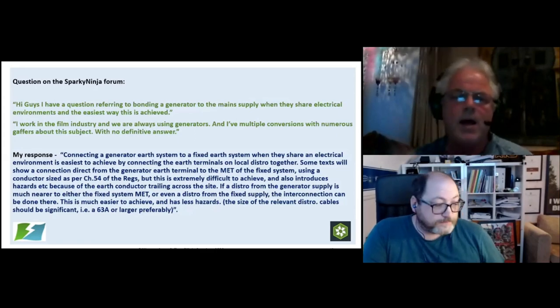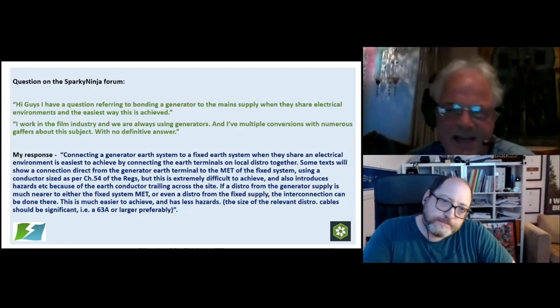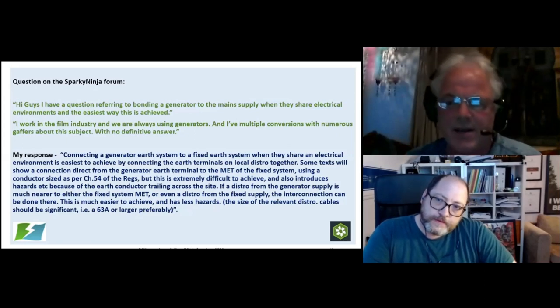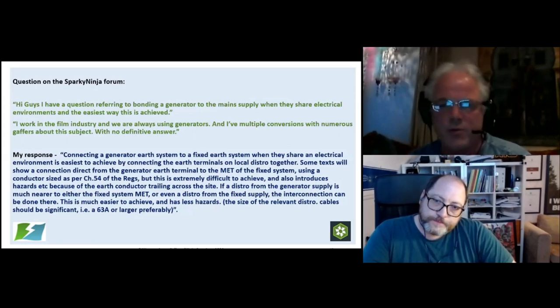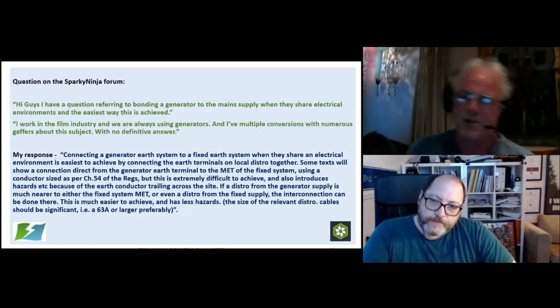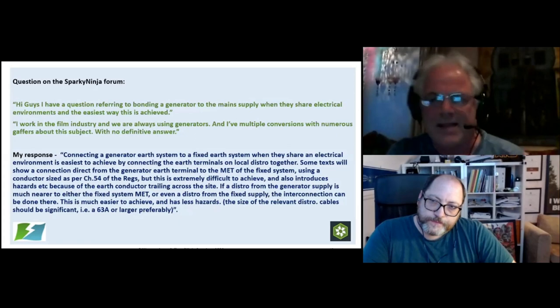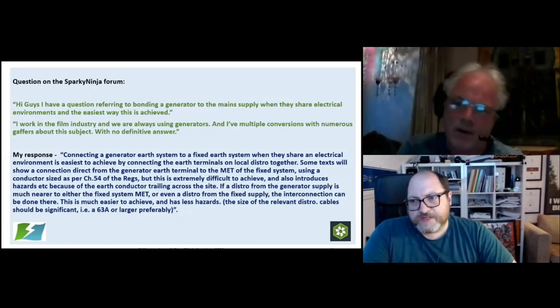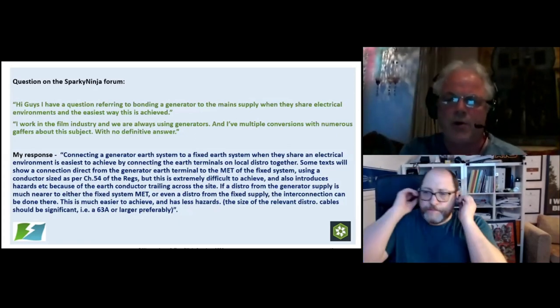Yeah. Mm-hmm. And what 7909 says is that we should link the earth systems together so that we don't get any differential between the earthing systems. Okay. The generator obviously is providing a supply. The generator has its own earth, right? A lot of the time nowadays, we put an earth rod in for a reference.